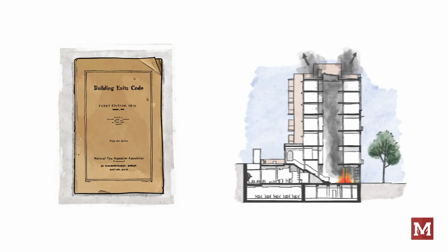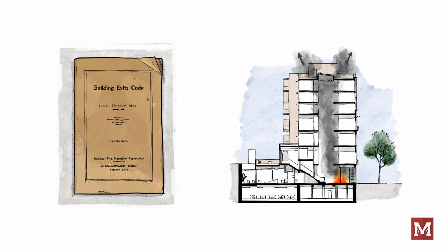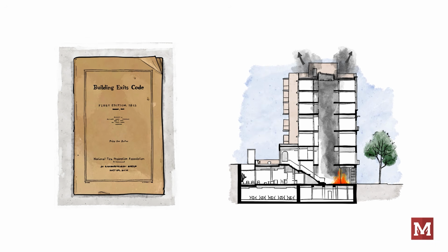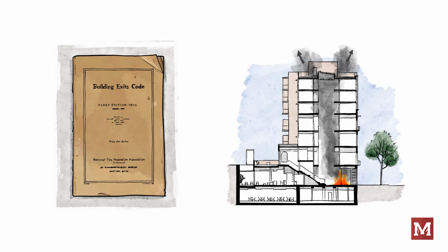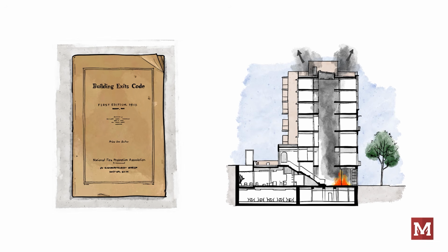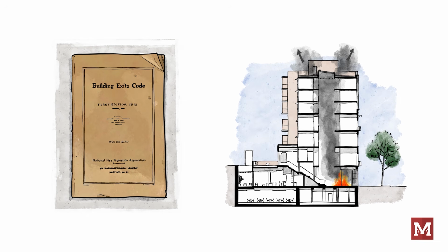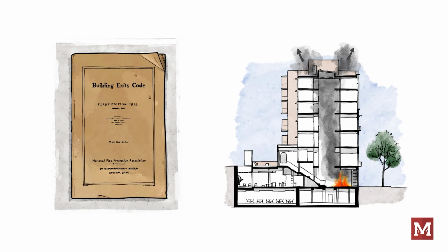were feasible. Could you do some modeling with today's software capabilities to prove that you can safely egress, say, 632 occupants on the floor of your designed building safely before conditions become unsafe, including a generous safety factor? You could. This would require the use of the alternative methods provision in the building code, but that's a heavy computational requirement, and there's no guarantee the modeling is going to give you the results you desire. In fact, it might say you need a 3rd or even a 4th exit. There's also the difficulty of familiarizing the AHJ with this method and getting them knowledgeable and comfortable with your analysis to approve your alternative method. It's probably just easier to add a 3rd exit.